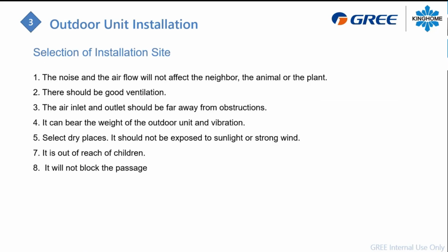Again, when you install this big unit outside, make sure you will not affect the neighbor in any way. So make sure you have a good site for the installation. Be sure you have good ventilation all around the unit so you will not recycle the air of the unit. The air inlet and outlet should be far away from obstructions, so not too close to the wall. We're going to see that in a couple of slides. Make sure you select a dry place, so as not to have too much water or ice falling on the unit. These are typical things you need to watch before you do your installation, also regarding safety.